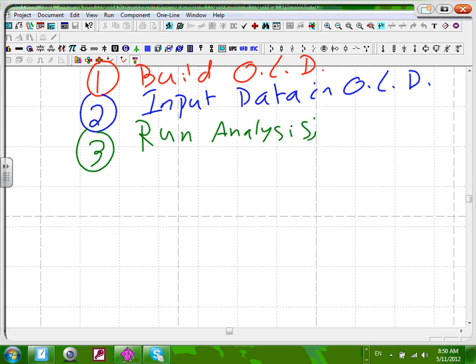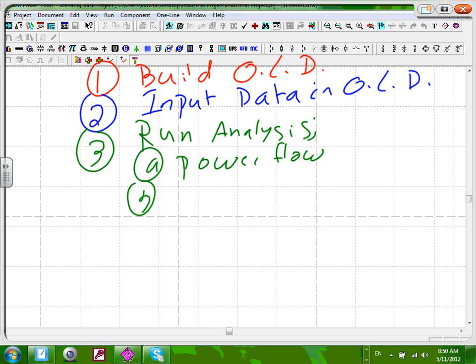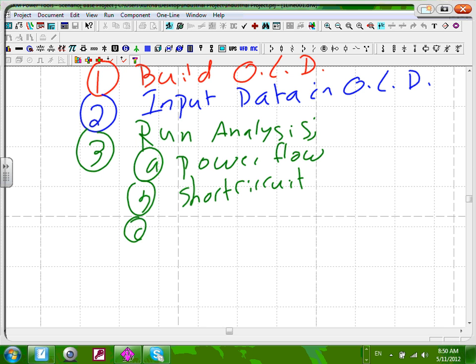Here's the analysis we're going to run. We can run a lot of analysis. A) We're going to run power flow. B) We're going to run short circuit — you're familiar with short circuit: three-phase, single-phase. C) We're going to do overcurrent protection coordination. The first two steps are really building the system. Step three is just pushing a button — done.